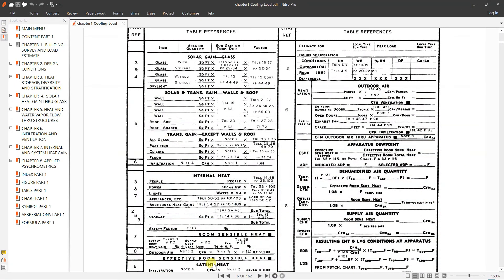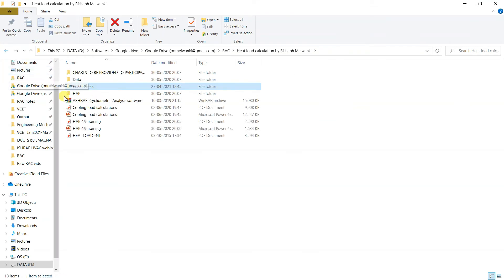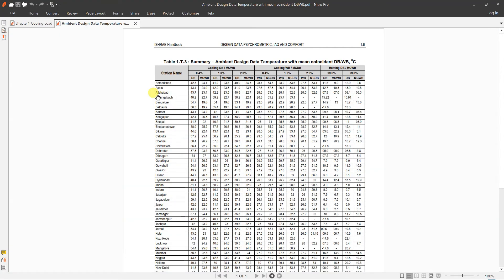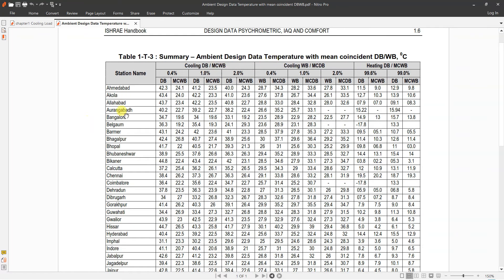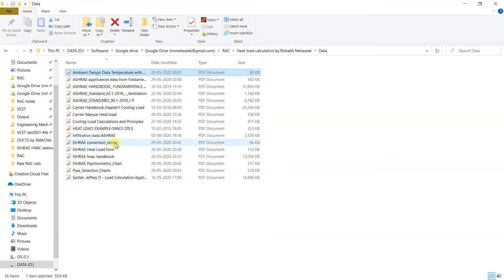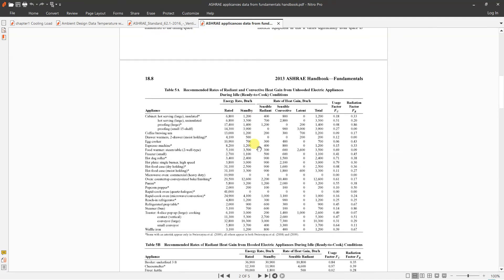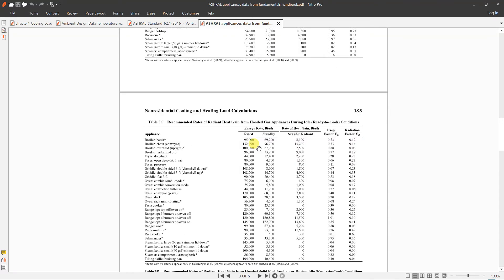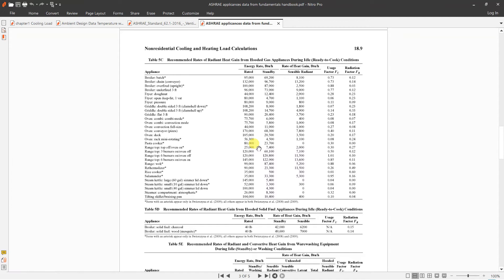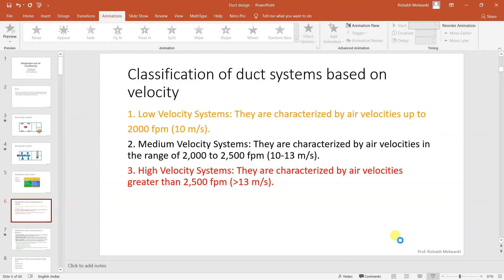To calculate the cooling load we have certain data from the ASHRAE handbook — like ambient design data for different cities with different dry bulb temperatures and other parameters. Similarly you can consider ventilation data and appliance data — if you are selecting a particular appliance, what should be the load. Using this data and the E20 Excel sheet we basically find what is the CFM, which is volume flow rate of air in cubic feet per minute. This forms the basis of duct designing.